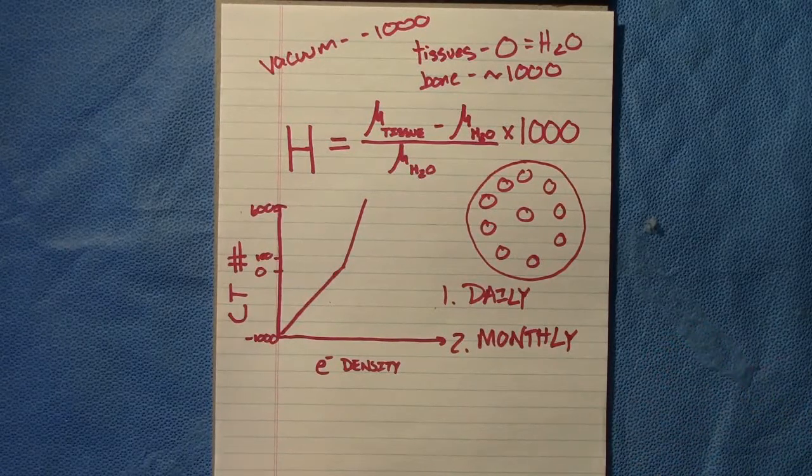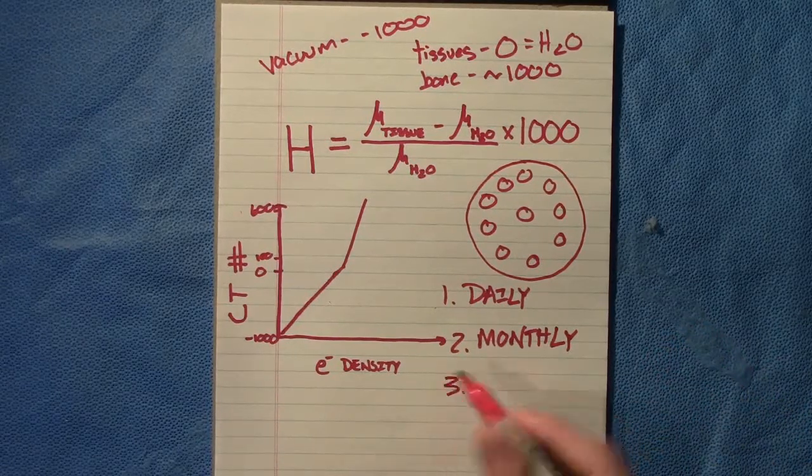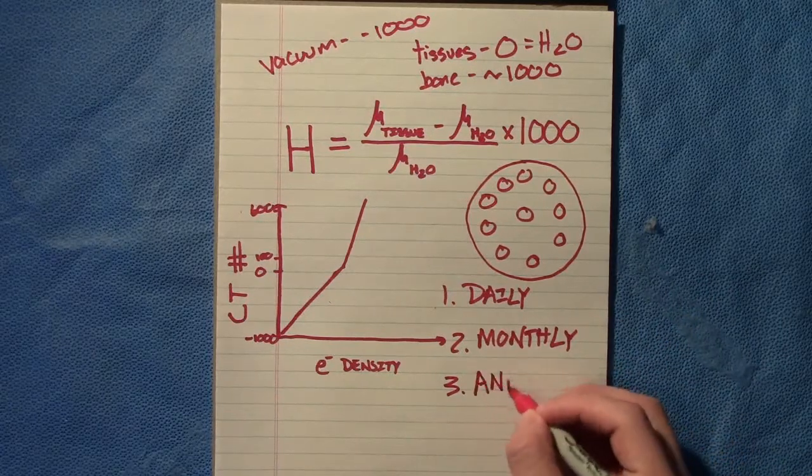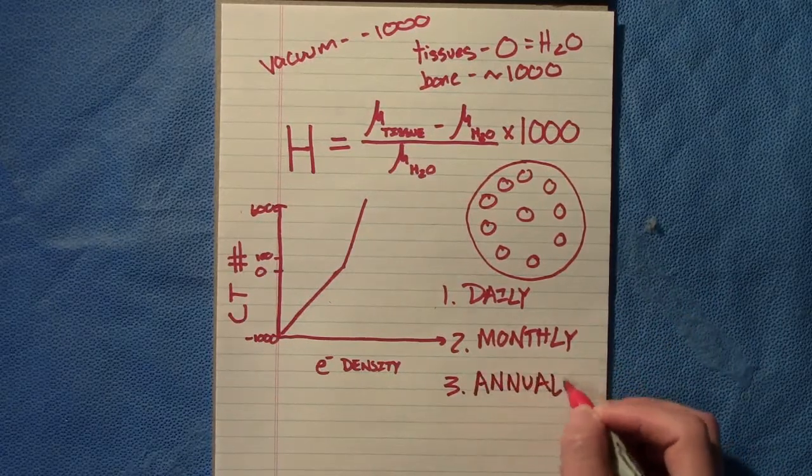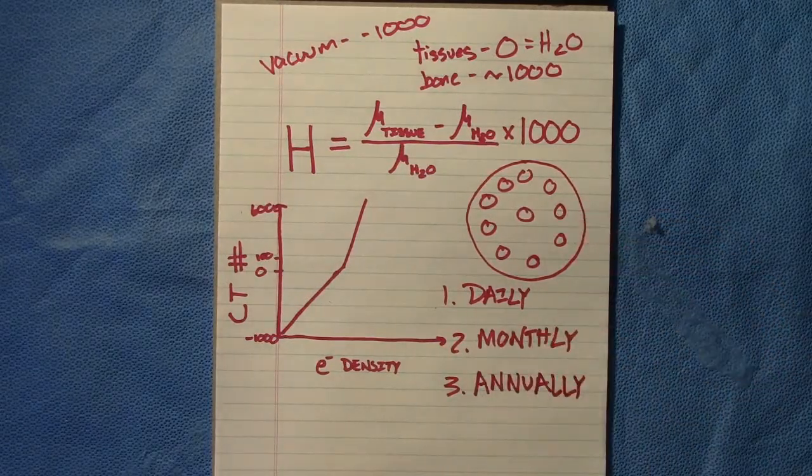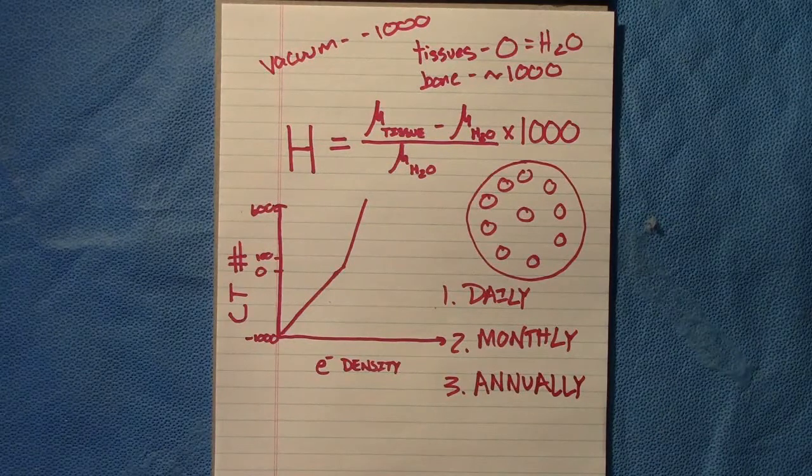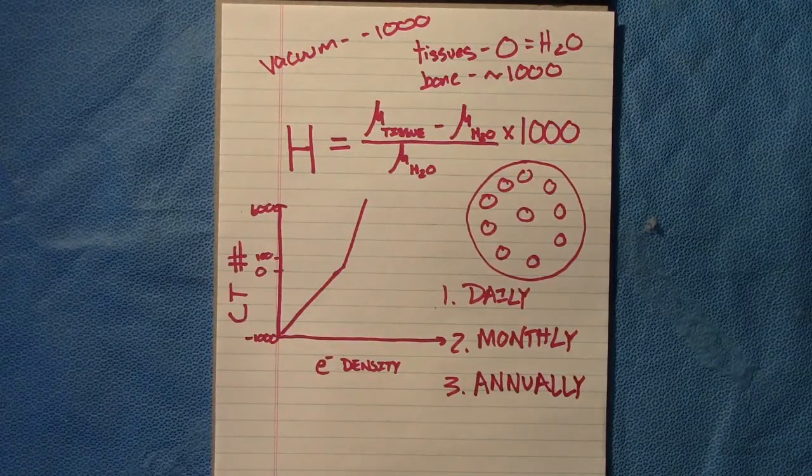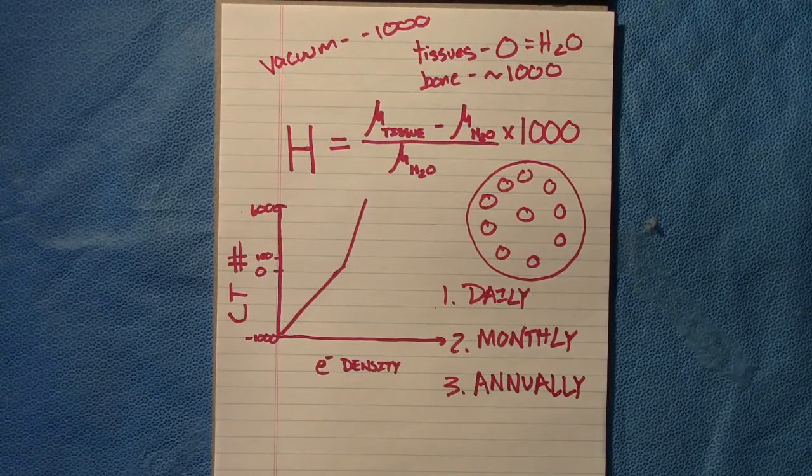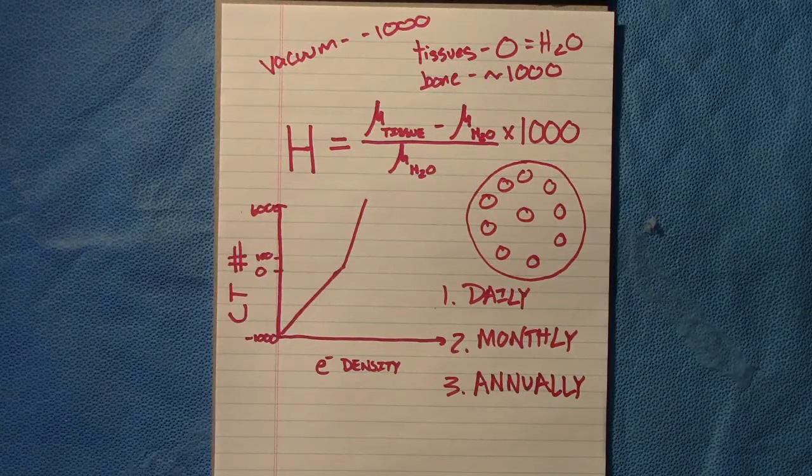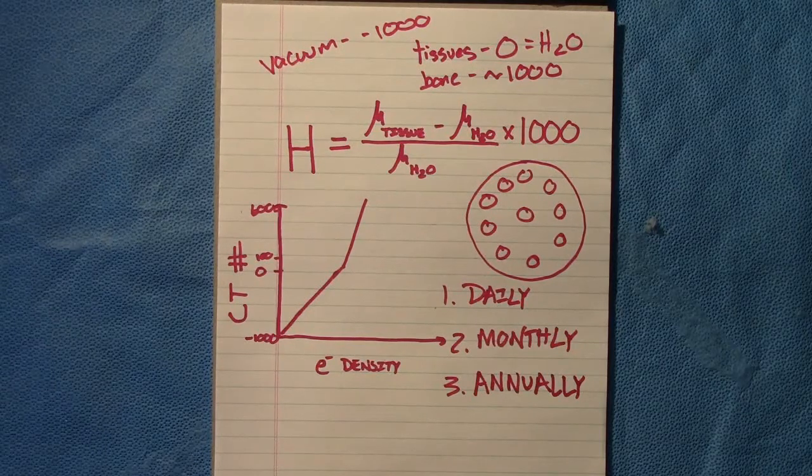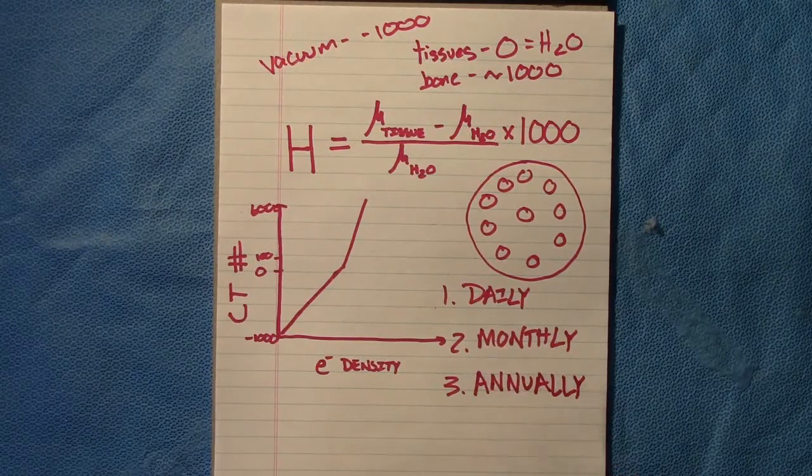And finally, annually, what you're going to want to do is actually take this Gammex phantom, completely scan it again, and verify that your electron density curve hasn't changed. Again, sometimes there's drift or different issues that you may need service for, but typically I've never seen one be off. However, you definitely need to test that annually because it is such a crucial step in radiotherapy.